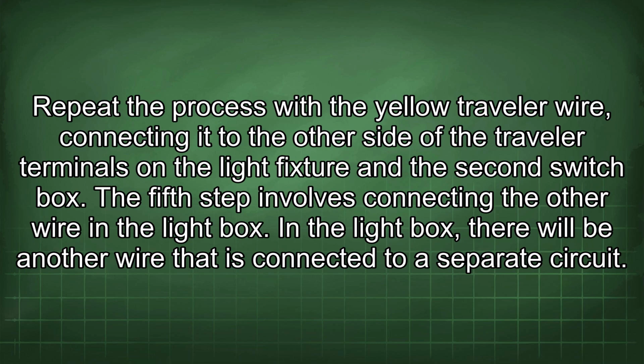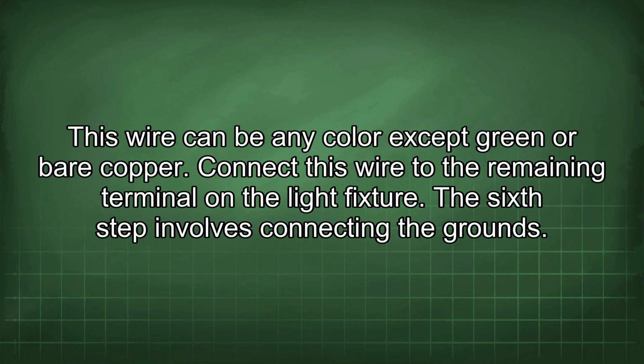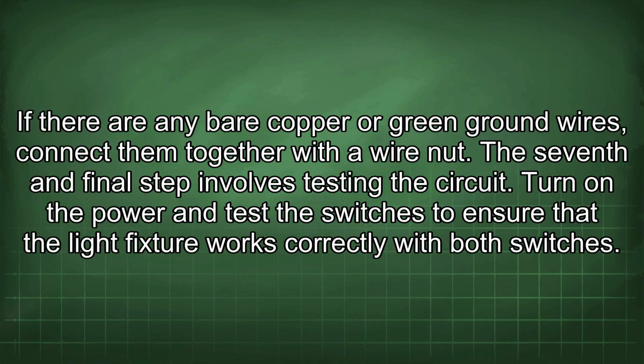The fifth step involves connecting the other wire in the light box. In the light box, there will be another wire that is connected to a separate circuit. This wire can be any color except green or bare copper. Connect this wire to the remaining terminal on the light fixture. The sixth step involves connecting the grounds. If there are any bare copper or green ground wires, connect them together with a wire nut.